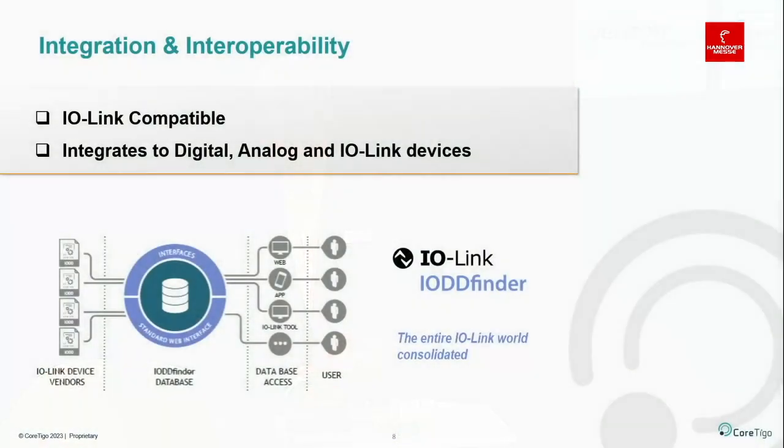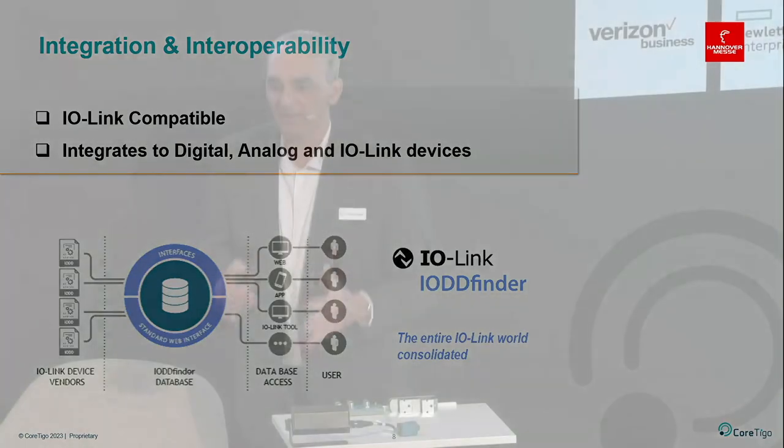IO-Link Wireless is part of the IO-Link standard, which provides integration and interoperability. It is completely IO-Link compatible — when connecting an IO-Link Wireless device, you get the IODD files and IO-Link structures automatically and seamlessly, with no configuration or code changes. Importantly, the path to IO-Link Wireless does not necessarily go through IO-Link. You can use a digital device, an analog device, or an IO-Link device — pretty much any sensor or actuator can be turned into IO-Link Wireless.